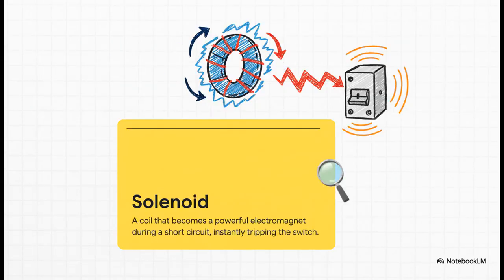But for a short circuit, you don't have time to wait for things to heat up. You need instant, split-second action. And that is the job of the short circuit sentinel, the solenoid. This is basically just a coil of wire. Under normal conditions, it does absolutely nothing. But when that massive surge of current from a short circuit blasts through it for a fraction of a second, it becomes a powerful electromagnet. And that magnetic force instantly snaps the switch open. It's a lightning-fast magnetic reflex, no waiting required.